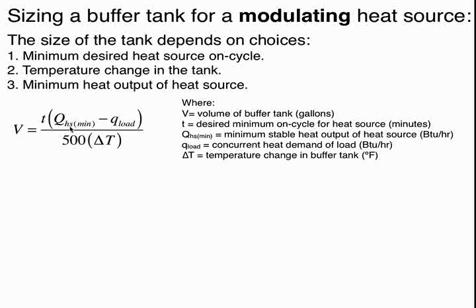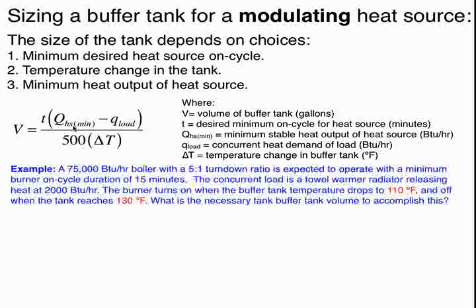Now, if it's a modulating boiler, the only thing that changes in the formula is the minimum heat output rate of the boiler. We're assuming that the boiler can go down to some minimum rate and have stable combustion conditions at that rate, as opposed to an on-off heat source which always has to operate at that peak output. So we'll do another quick example. Let's say, again, it's a 75,000 BTU per hour boiler, same peak output, but it has a 5-to-1 turn-down ratio, which implies it can go down to 1/5 of its rated output.